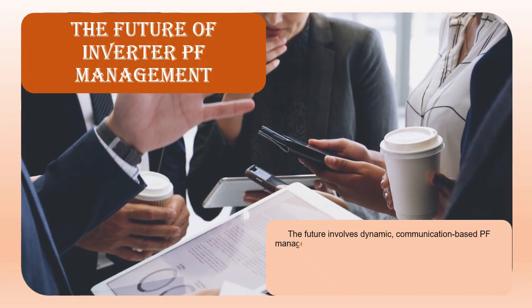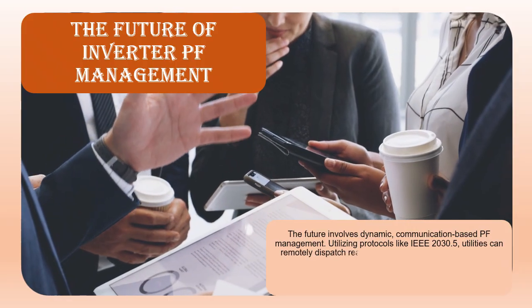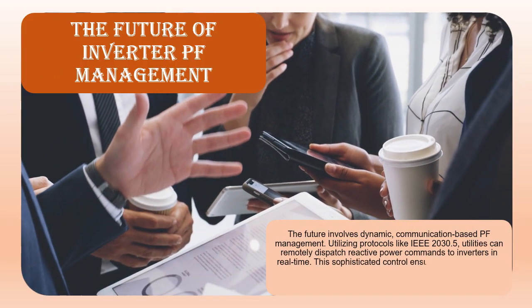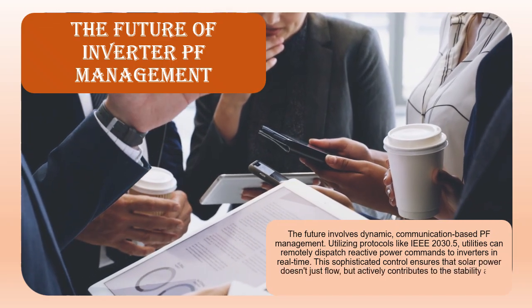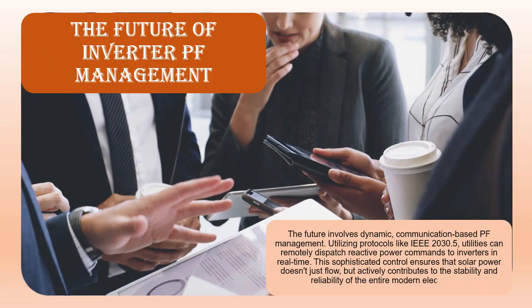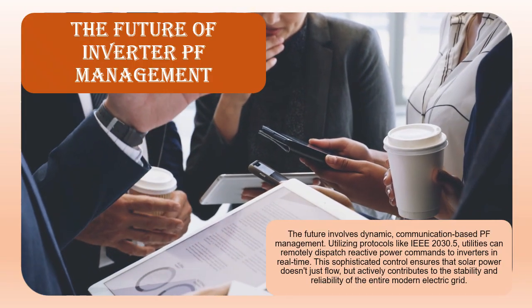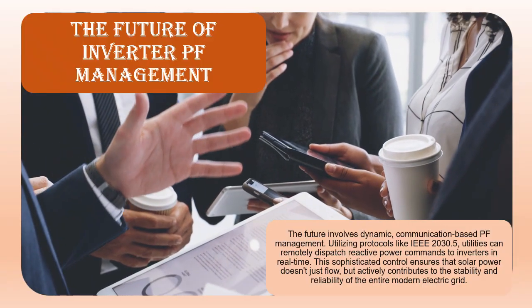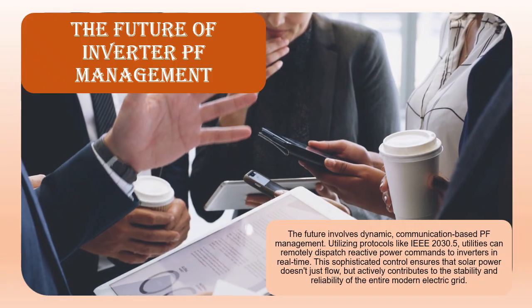The future of inverter PF management. The future involves dynamic, communication-based PF management. Utilizing protocols like IEEE 2030.5, utilities can remotely dispatch reactive power commands to inverters in real time. This sophisticated control ensures that solar power doesn't just flow, but actively contributes to the stability and reliability of the entire modern electric grid.